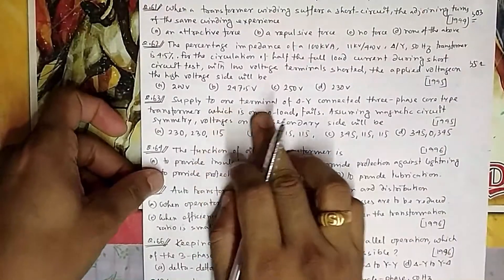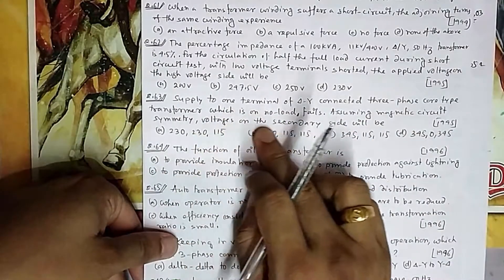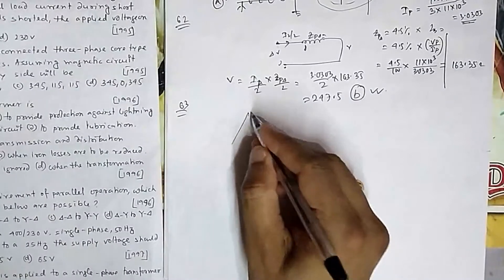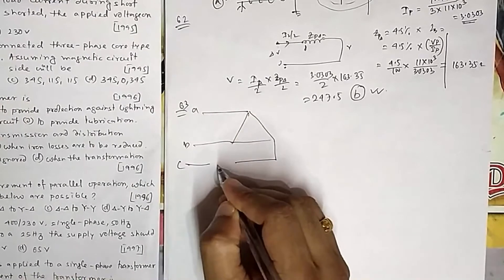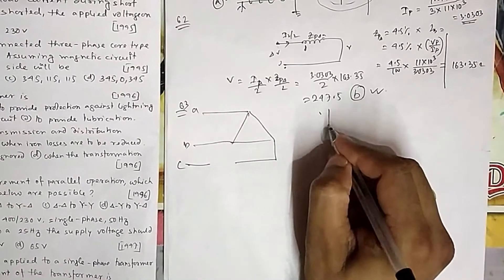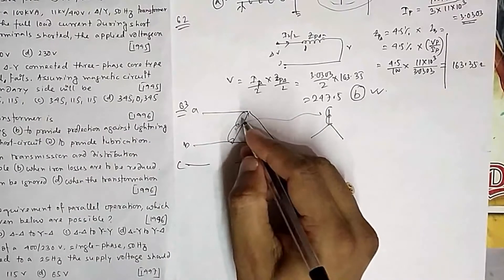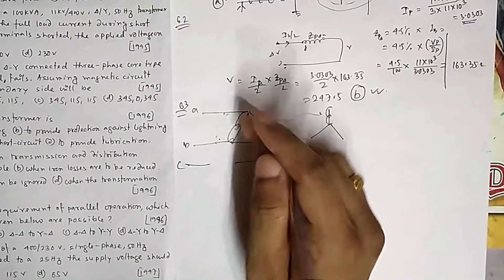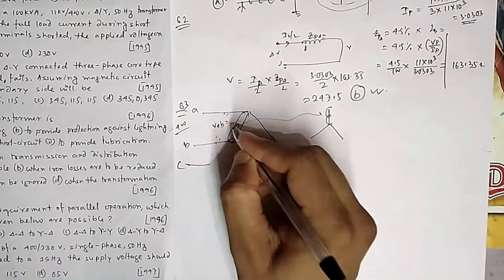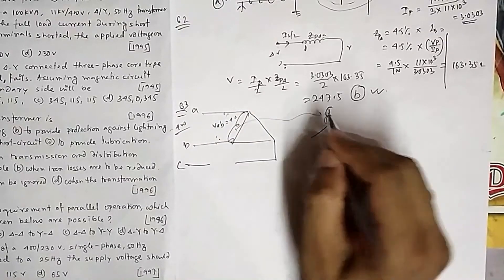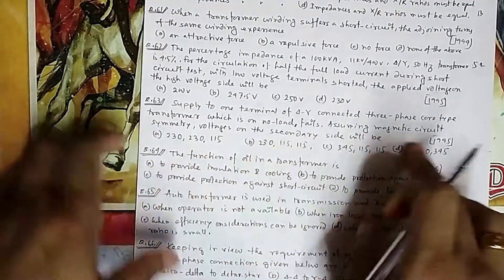Question 63: Supply to one terminal of a delta-star connected three-phase core-type transformer on no-load fails. Assuming magnetic circuit symmetry, the voltage on the secondary side will be — so it is a delta-to-star transformer. Suppose phase C supply is cut. The winding corresponding to phase A-B is still getting the full line-to-line voltage V_AB, which is 400 V. So that winding gets its full rated voltage.